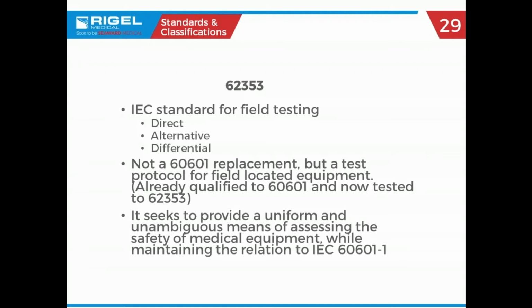Differential is a neat way to go. It's very safe. And all we're doing in differential is saying, I'm looking at the current going into the unit on the hot wire, black. I'm looking at the current coming out on the neutral wire, the white wire. The difference between those two is my leakage current. Makes sense. Very simple, easy test. But you have to be utilizing the 62353 test standard to do that. All right, so what did I miss on here? No, I haven't missed anything.